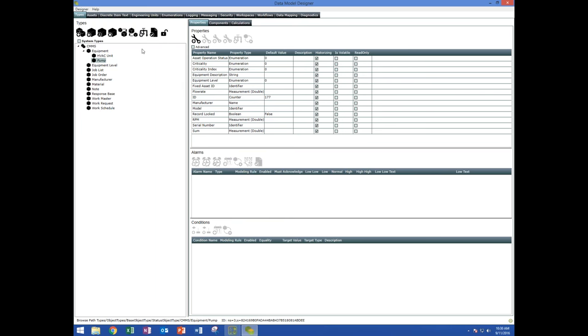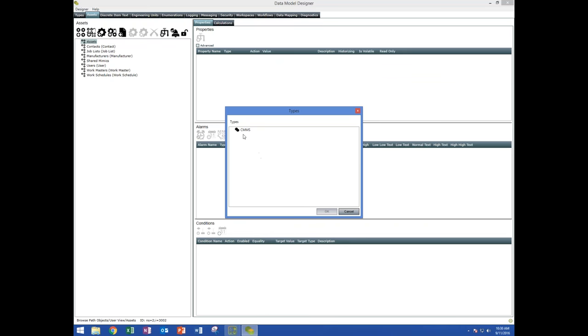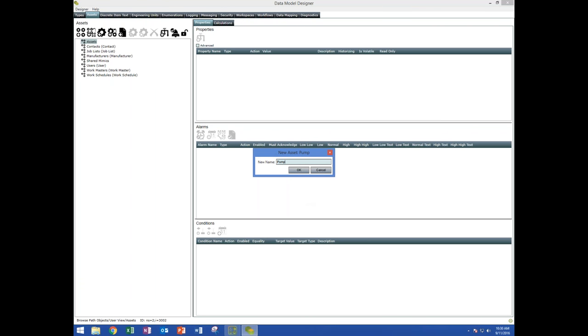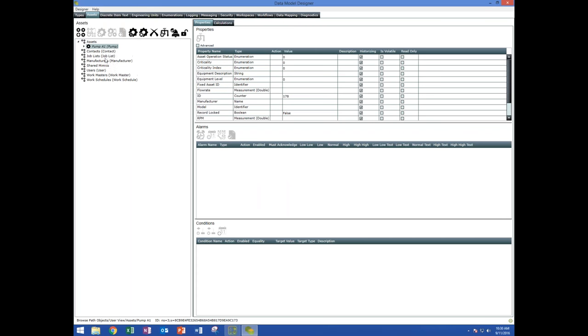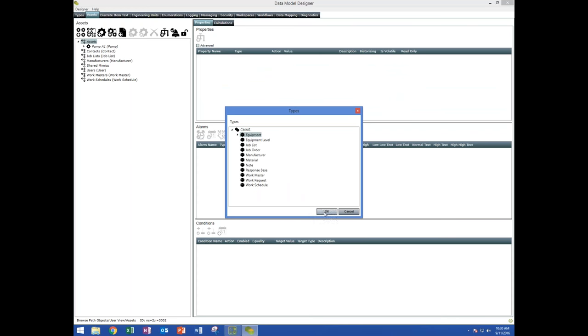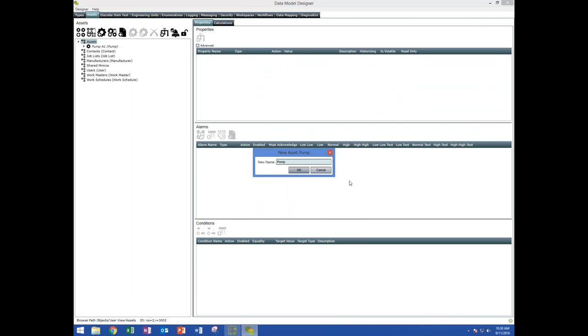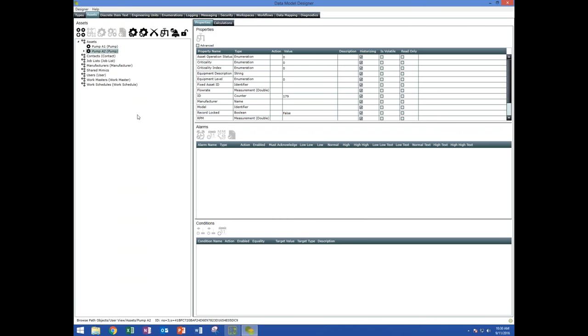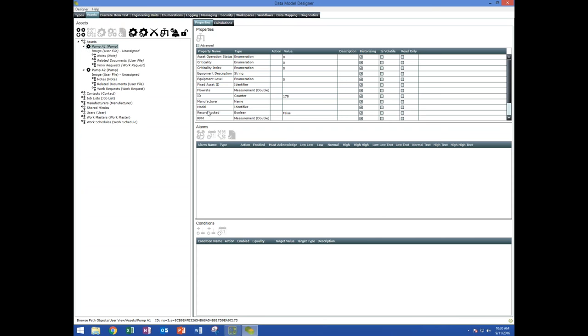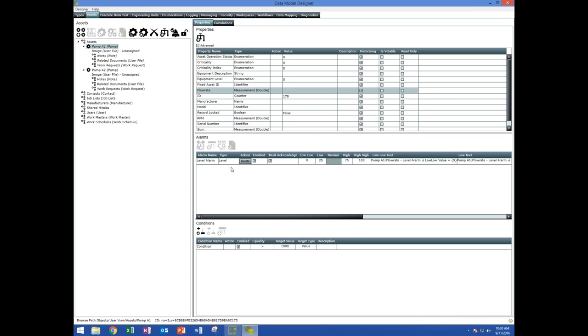Once you've got your types created, you create instances of the types — these are the real-world assets you're interested in monitoring. I'm going to create two pumps: pump A1 and pump A2. Now I've got two assets in my system. If I look at the flow rate on these assets, I can see I've got my alarm, my condition, and all the default values I set are kept — my calculation has been created automatically. All the settings defined in my type are picked up as you create instances. If you are monitoring a large number of similar assets, this has just saved you hundreds and hundreds of hours.